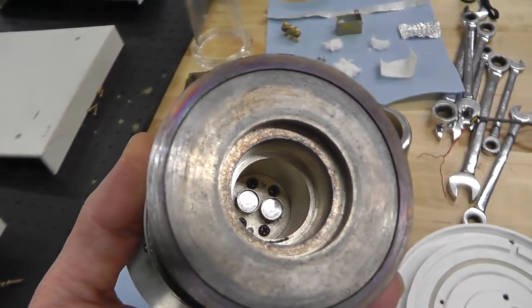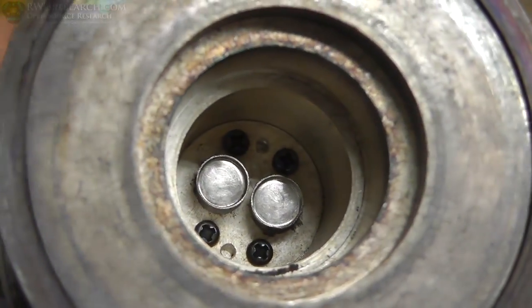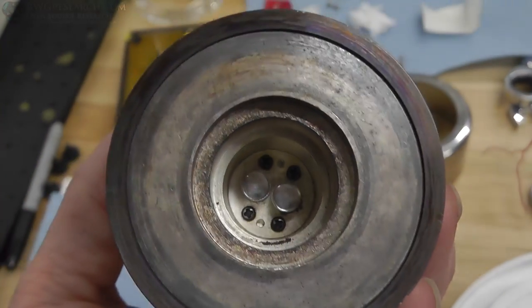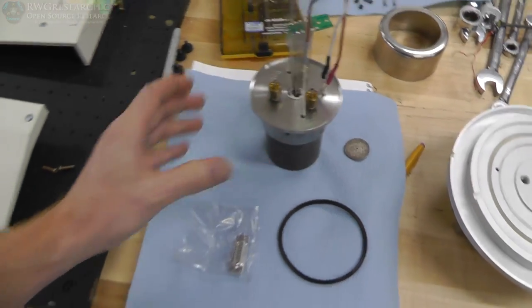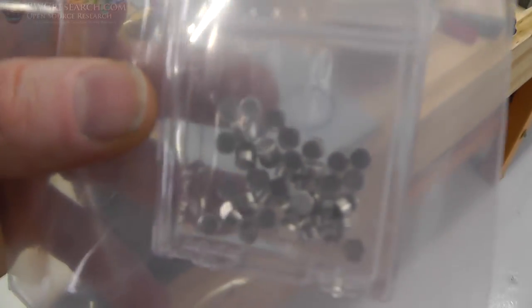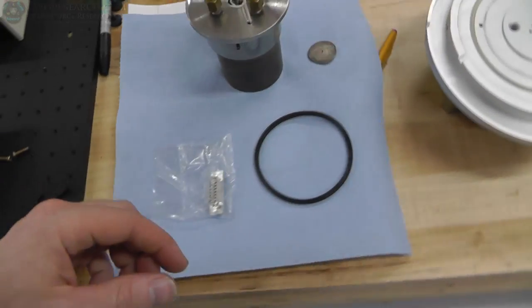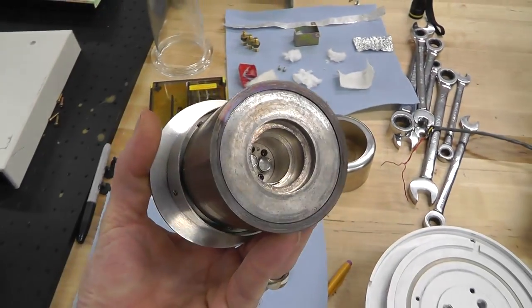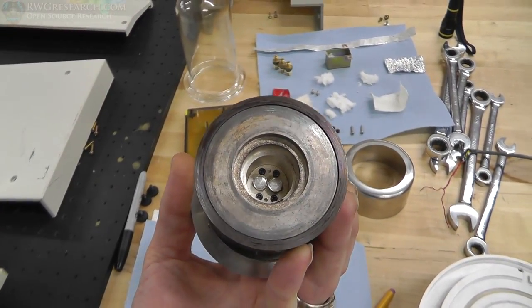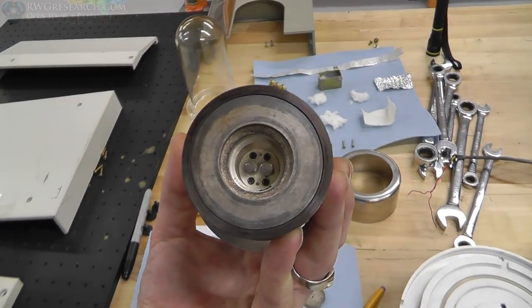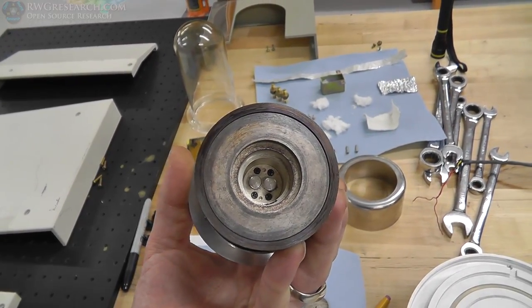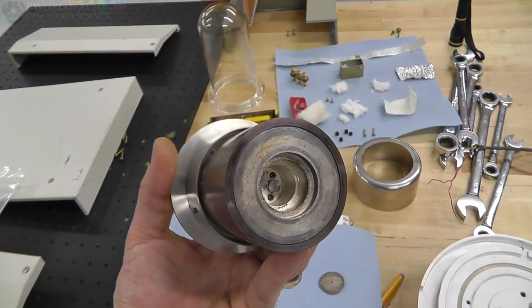If you look inside of here, there are two tiny sample holders. You actually put your sample inside of a small pan - aluminum, silica, alumina or some other type. Currently, I have aluminum pans. They look like this and they just sit inside there and your sample sits on top of them. You basically flow a gas over top of these, usually air or argon or an inert gas. And you just measure the difference in the heat exothermic or endothermic as you heat it.